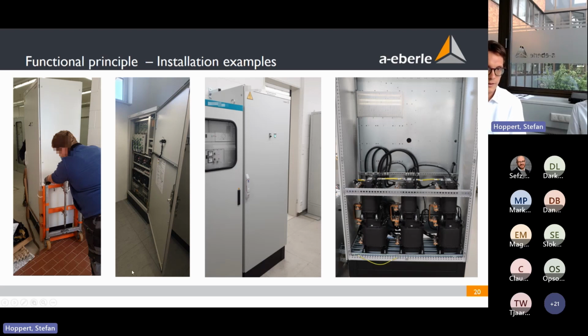And here we see the cabinet in the second picture as it is in the open state, and here when it's closed, so it looks like a normal indoor cabinet. And as Stefan said, the transformers are on the back side. Here we see the 3 phases. For each phase we have 2 transformers, the bigger one on the bottom and the smaller one on the top. This will always be on the back side. So from the front, it's not visible, and for the service it's not necessary to see it. It's also good for the heating, that the heat coming from the transformer is on the other side of the system. This makes it easy for installation, so you have no contact with the transformers.